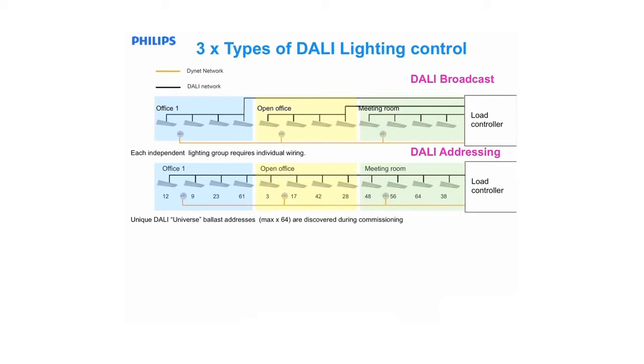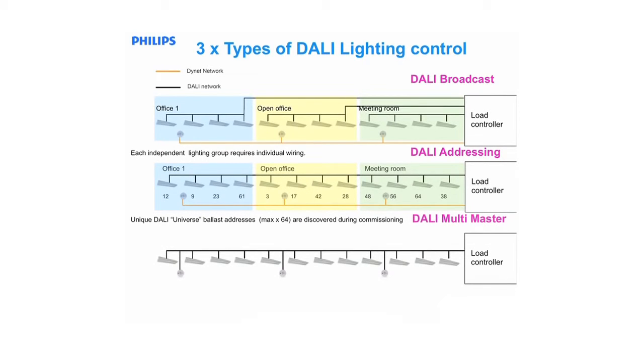In the DALI MultiMaster system, the Dynalite network has been completely removed. The sensors are directly connected onto the DALI network already used for lighting. This allows the lighting control system to have the same network control of the sensors by utilising the existing DALI network. The DALI MultiMaster sensors are completely powered from the DALI network, removing any need for additional power cabling.